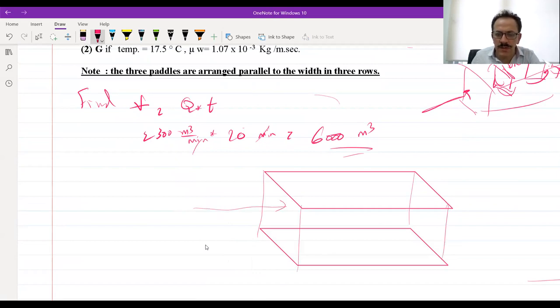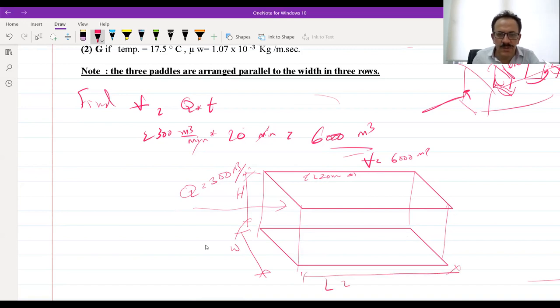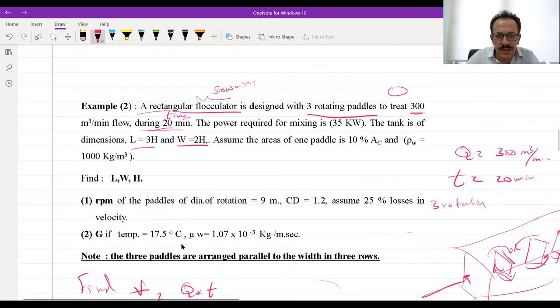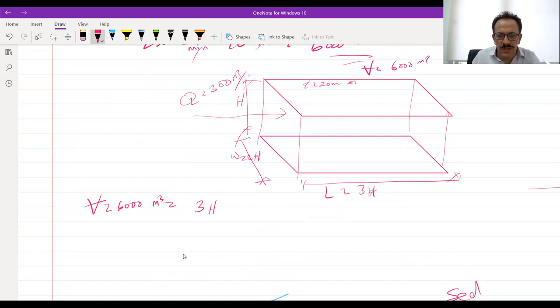After finding the rotation per minute, we calculate G. G equals the square root of P / (Volume × μ): P = 35 kW, Volume = 6,000 m³, and viscosity of water at that temperature. The result is between 10 to 80 per second — within the acceptable range, meaning we are within the slow mixing design standards.